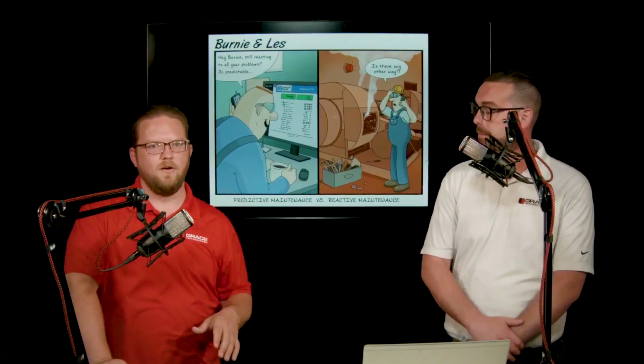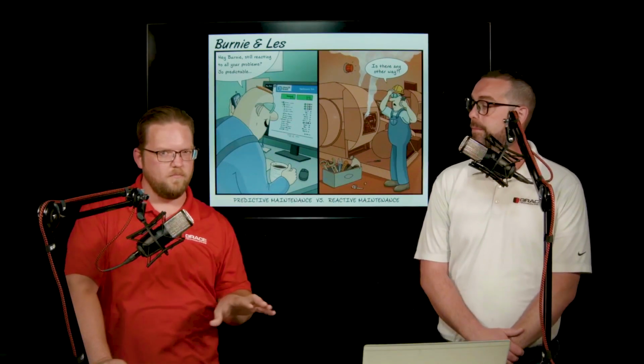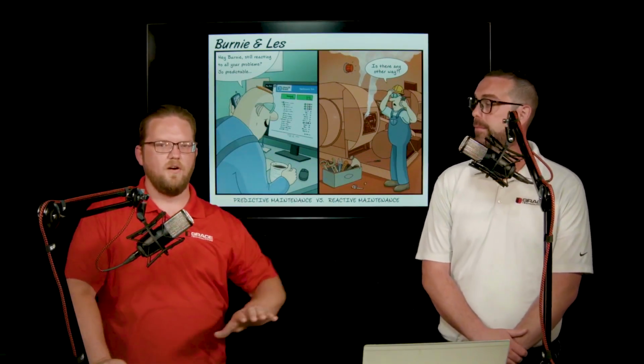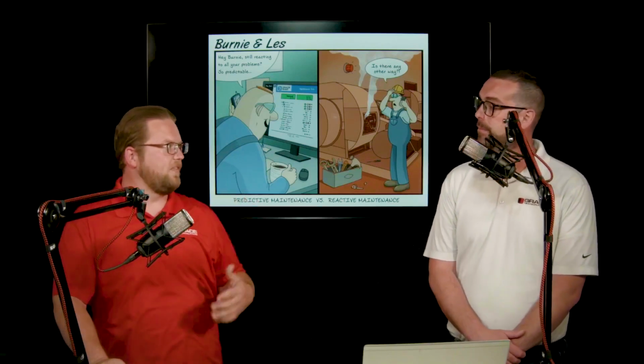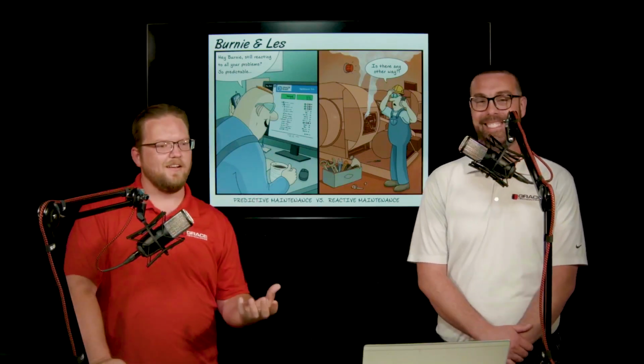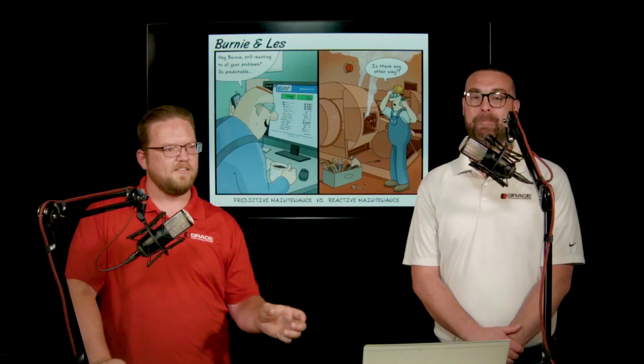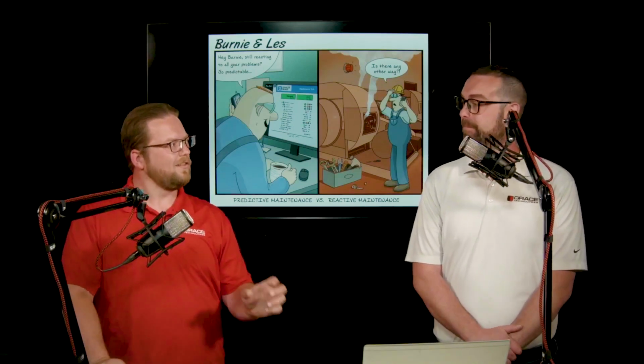The standard piece you're referring to is our vibration and temperature node, and we have a couple models depending on the frequency of detail you need. What that's going to do is monitor the surface temperature and vibrations from any of your rotating assets. Vibrations are where you're going to first see signs of an issue - before you're able to physically see any movement, before you're able to feel any temperature or notice anything with your human capabilities, these are going to identify changes in that vibration and start to alert you.